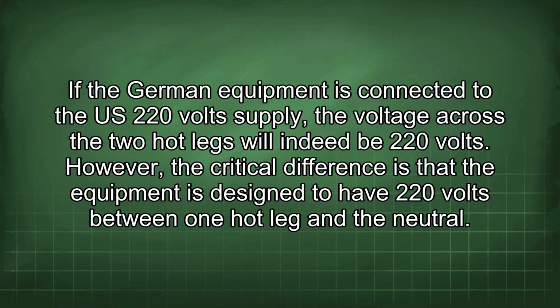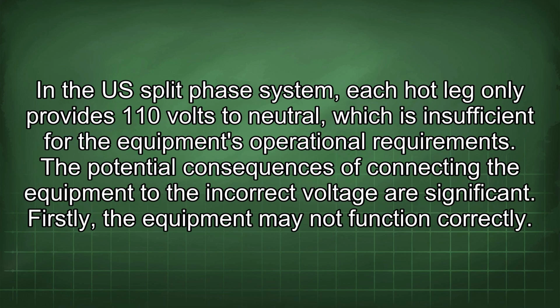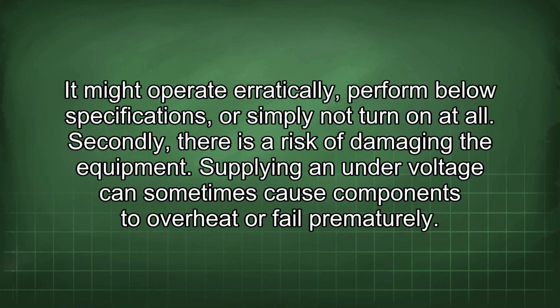However, the critical difference is that the equipment is designed to have 220 volts between one hot leg and the neutral. In the US split-phase system, each hot leg only provides 110 volts to neutral, which is insufficient for the equipment's operational requirements. The potential consequences of connecting the equipment to the incorrect voltage are significant. Firstly, the equipment may not function correctly. It might operate erratically, perform below specifications, or simply not turn on at all.